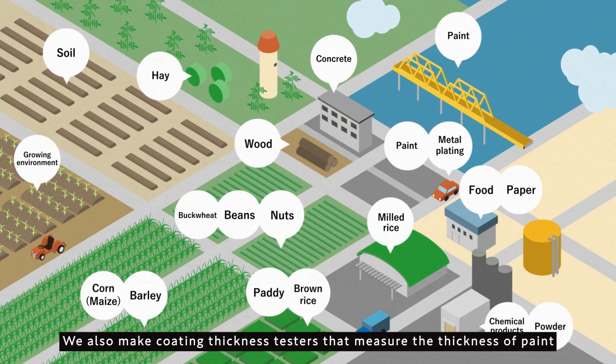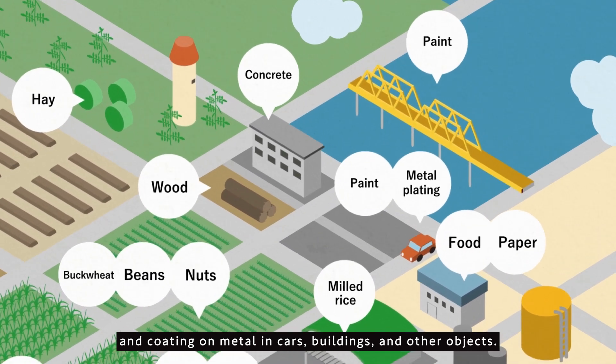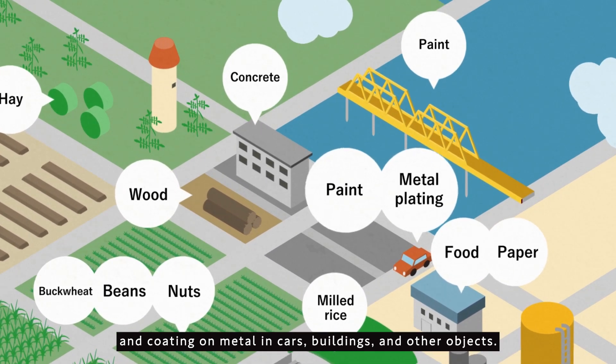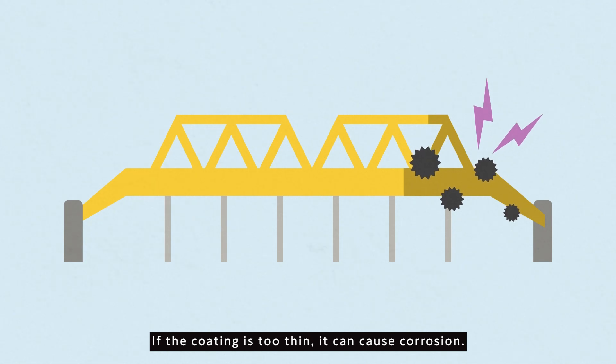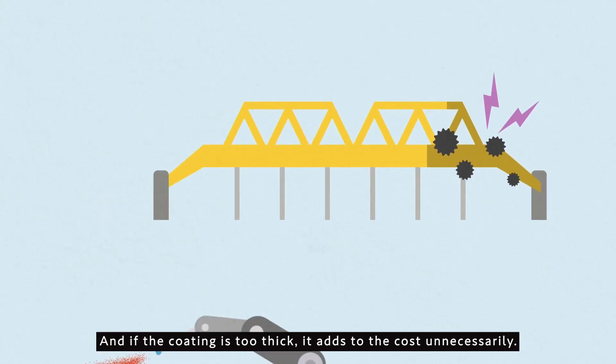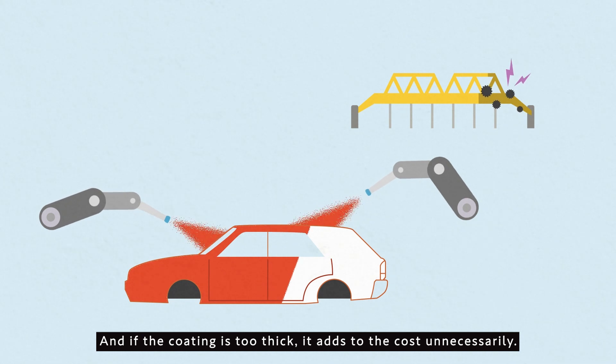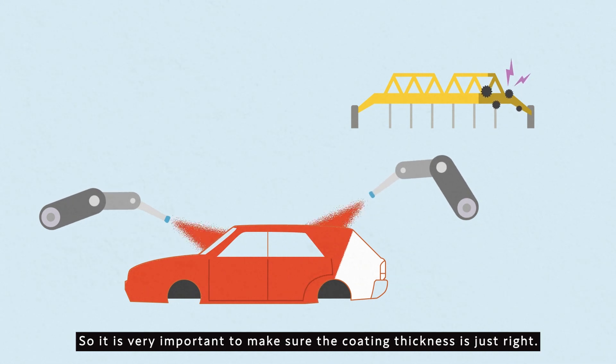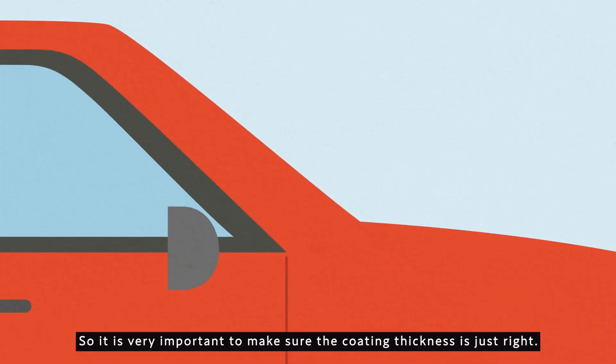We also make coating thickness testers that measure the thickness of paint and coating on metal in cars, buildings and other objects. If the coating is too thin, it can cause corrosion. And if the coating is too thick, it adds to the cost unnecessarily. So it is very important to make sure the coating thickness is just right.